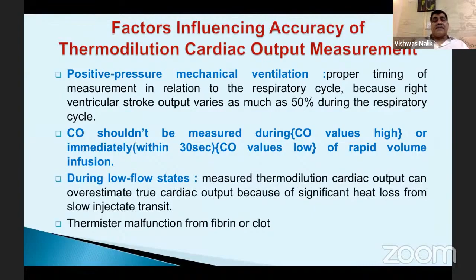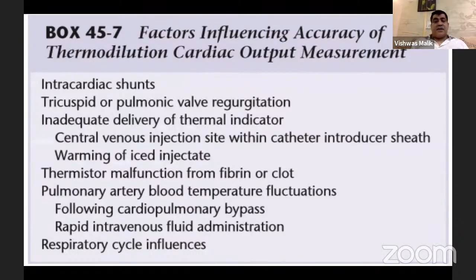Similarly, during low flow states, since there will be less transit of the indicator, it might overestimate the cardiac output values. There can be a fibrin or a clot on the thermistor site, the distal site, and there can be sensing problems in the thermistor. So now, to summarize, intracardiac shunts, tricuspid or pulmonary valve regurgitation, inadequate delivery of the thermal indicator because of excessive volume administration, thermistor malfunction from fibrin clot, or pulmonary artery blood temperature fluctuation during cardiopulmonary bypass can interfere in the accurate measurement of thermodilution cardiac output.